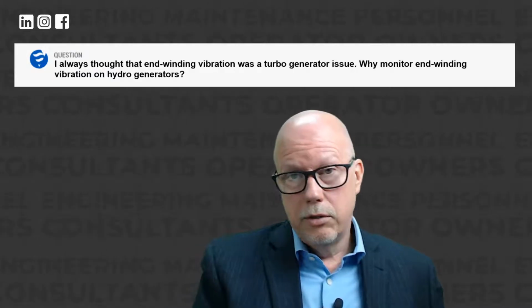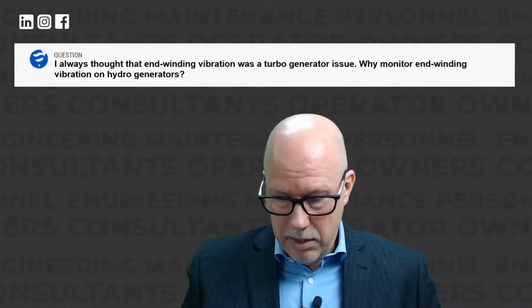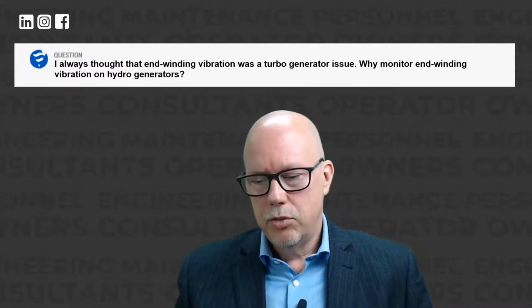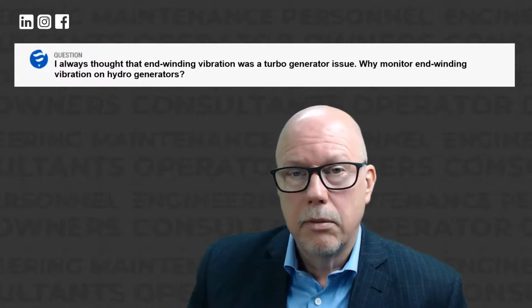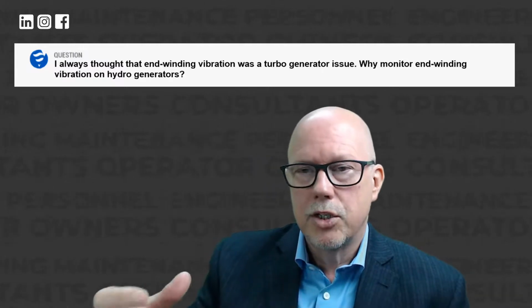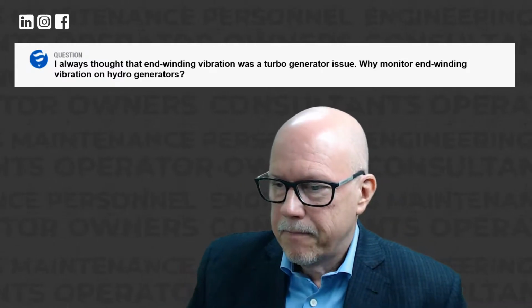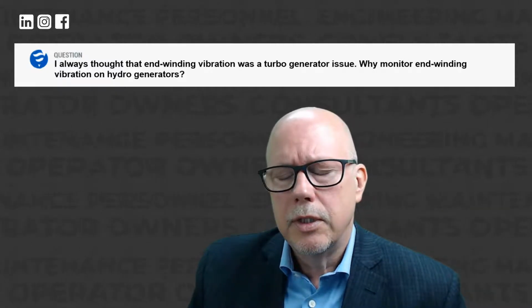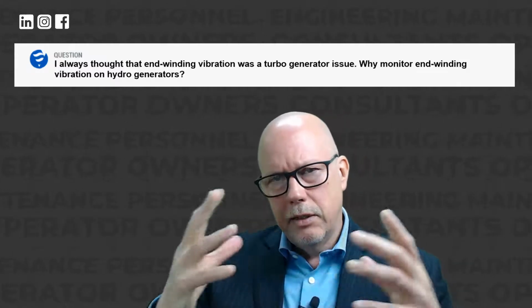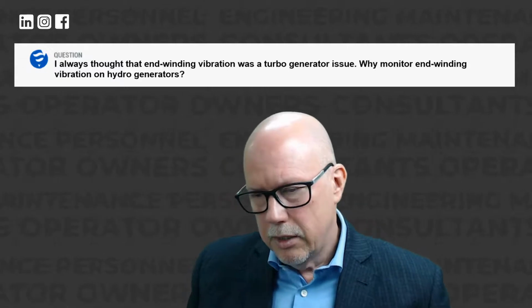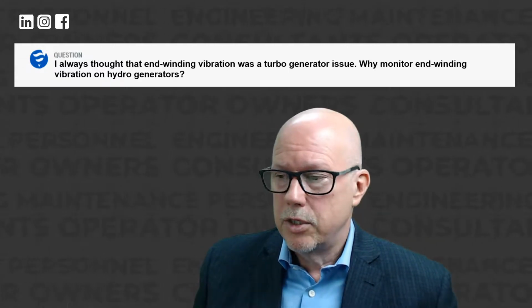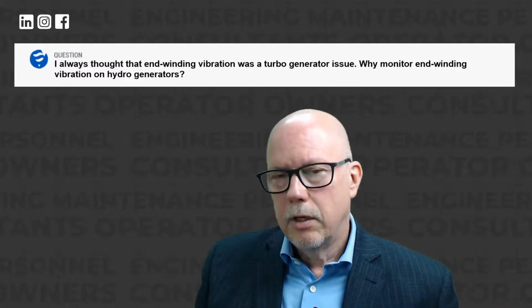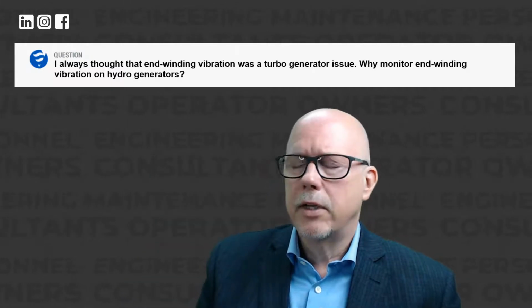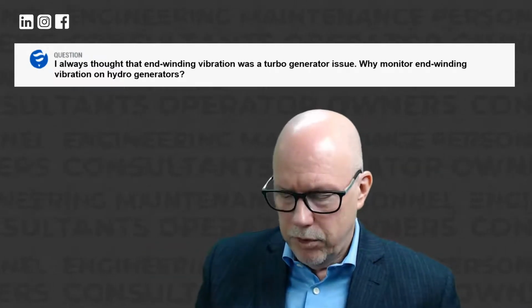And they couldn't understand why this unit was having so many issues because they didn't seem to have these issues with the other units. In reality, they installed the same equipment on another unit just to have a reference. It confirmed that this particular unit had serious vibration issues, and it also corroborated some thermal mapping that they did, where they could see the insulation was deteriorating. It was getting hot spots everywhere. In the end, they were able to use the fiber optic accelerometers to understand exactly what was going on. An interesting thing is that it's common for this power station to run out of water during the summer. And they could see the vibration of some of the windings increasing significantly. I think one was up to like 9 Gs at 120 hertz, which is significant.